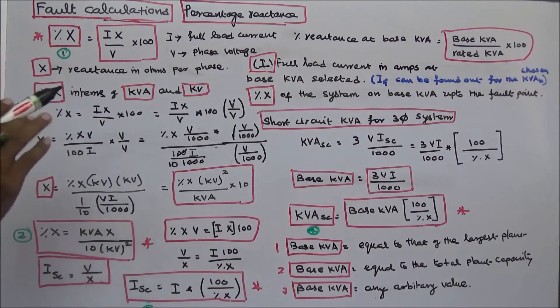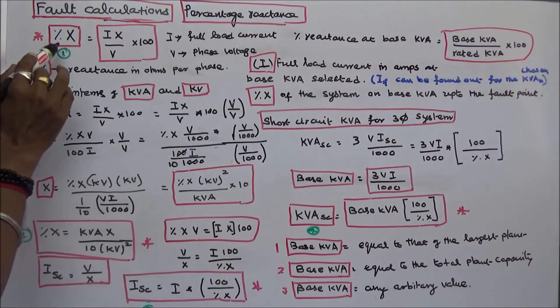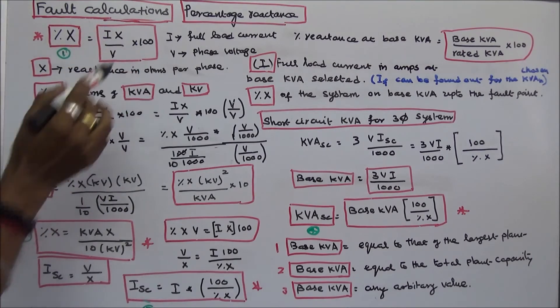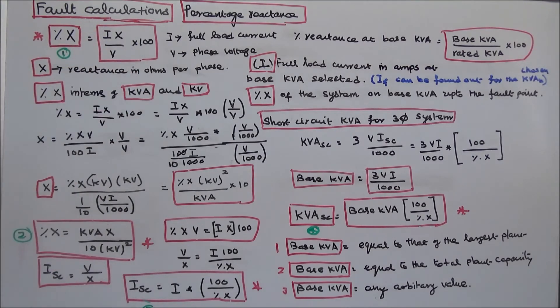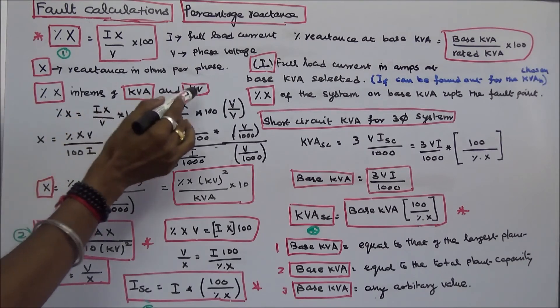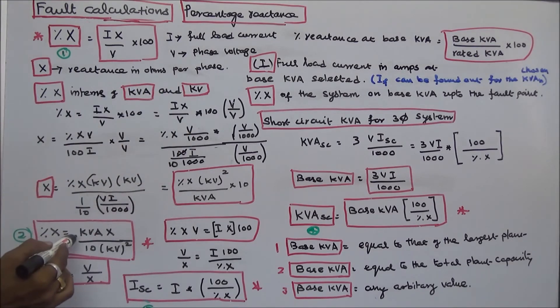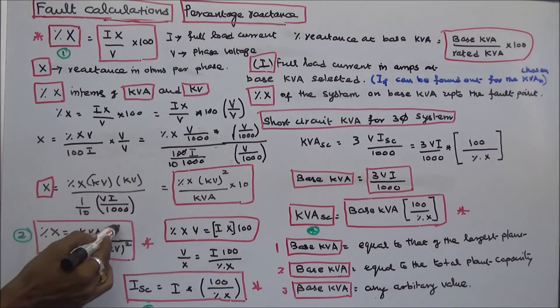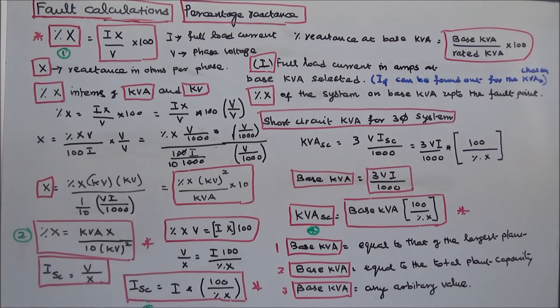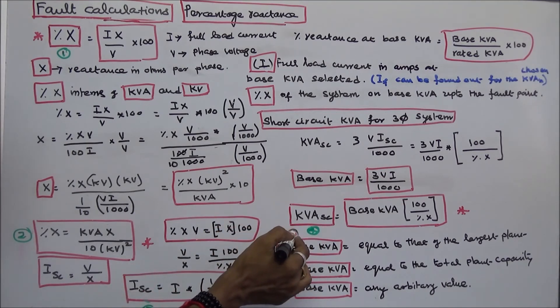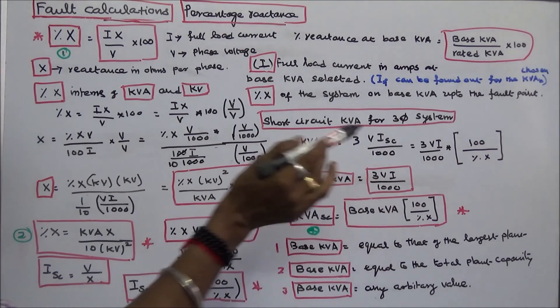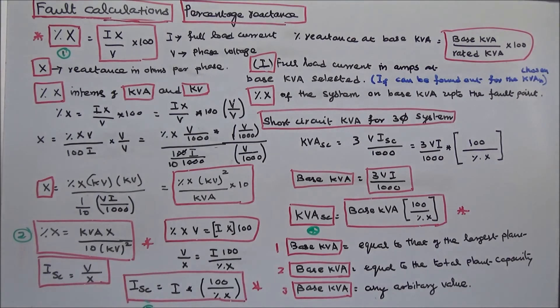In summary, there are four key formulas. First, percentage X equals I times X divided by V, times 100. Second, percentage X equals KVA times X divided by 10 times KV squared. Third, short circuit current ISC equals I times 100 divided by percentage X. Fourth, short circuit KVA equals base KVA times 100 divided by percentage X.